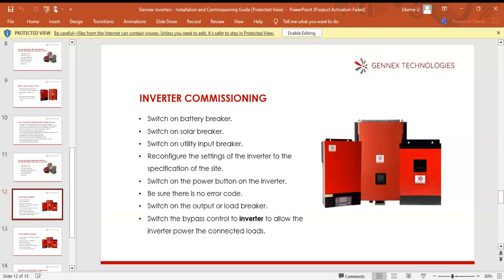Switch on the output or load breaker. Then switch the bypass control to inverter, because you will have labeled one side of your bypass control as bypass and the other side as inverter. If it is on bypass, even when the inverter is on, you won't get any output to power the building. So it has to be switched to the inverter side. Your bypass switch is like a changeover between direct supply and the output of the inverter.